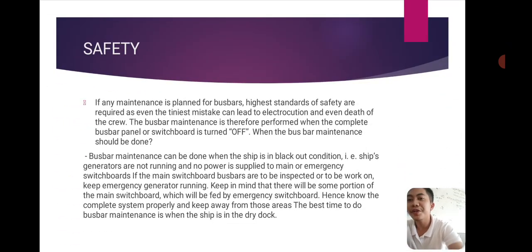Safety. If any maintenance is planned for bus bars, higher standards of safety are required, as even the tiniest mistake can lead to electrocution and even death of the crew. The bus bar maintenance is therefore performed when the complete bus bar panel or switchboard is turned off. When should bus bar maintenance be done? Bus bar maintenance can be done when the ship is in blackout condition.